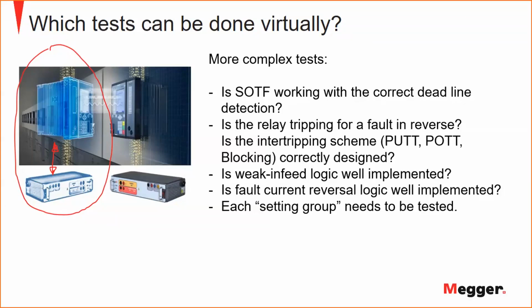Weak infeed logic is also a sort of inter-tripping scheme. Current reversal logic, that is very tricky because there are some timers there. It can be worth having a look in detail with the disturbance recorder. And especially keep in mind that if you are running 4 or 5 setting groups, you have to test all of them. So the setting groups are beautiful, but they are bad because you have to test all of them. And once you have performed your tests for setting group number 1, with small changes you can perform them for setting group 2, 3, 4.